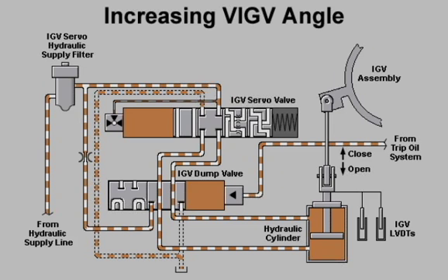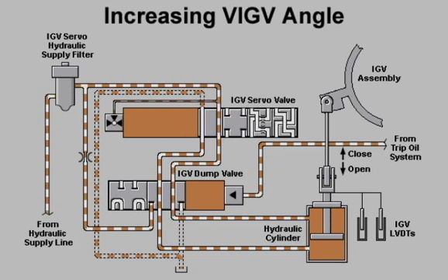If the VIGV operating sequence requires a greater variable inlet guide vane angle, the control system will shift the spool valve of the IGV servo valve to a position which allows hydraulic fluid to flow to the upper section of the hydraulic cylinder. Hydraulic fluid from the lower section of the hydraulic cylinder is dumped to drain.